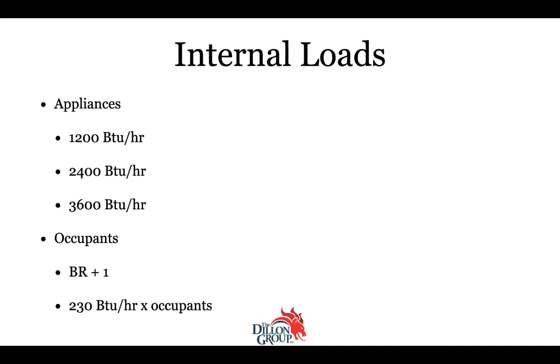ACCA has been kind of backing off on this a little bit. Not in their manuals, but in some of their programs, they say if they have one extra person in the house, that's not a big deal. It's not a deal killer because it's only 230 BTUs per hour. So ACCA gives some soft guidance: if you've got a three-bedroom house, it should have four people in the Manual J load calculation. But if they have five, it's not bad. At least you got a load calculation and it's close. That's the internal loads that get looked at.